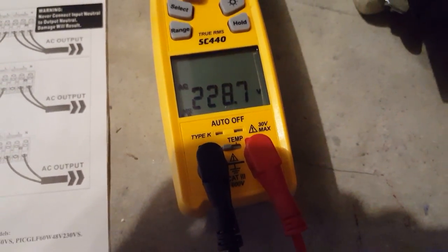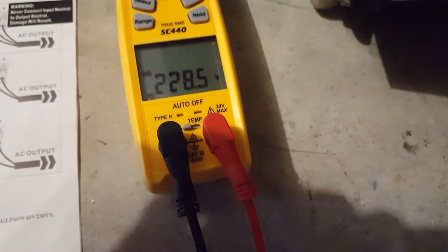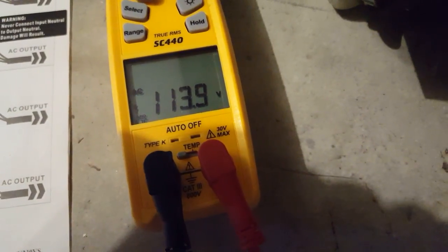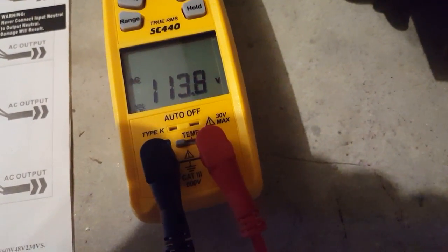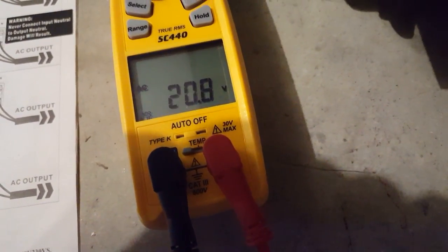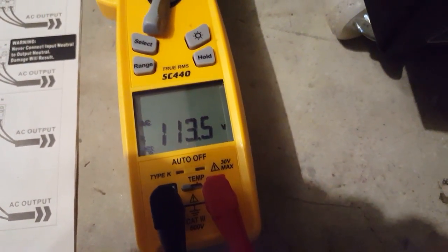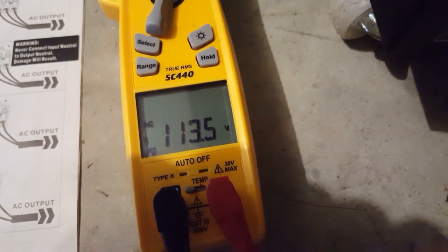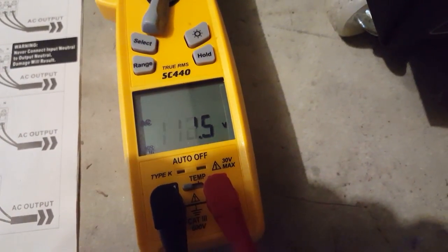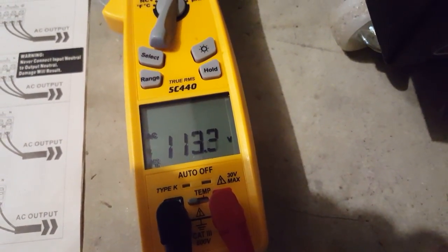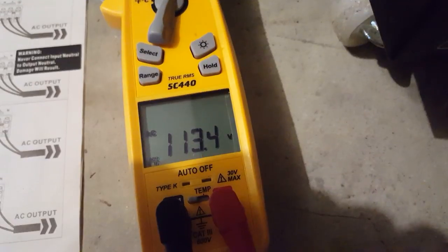What's different about this inverter versus other inverters, it can separate the voltage. So right here we were checking the voltage, right. So now I'm going to go to the neutral leg. And look, we got 113 volts. Let's stay on the neutral leg and go to the other leg, and it's another 113 volts. It stays at 113 volts and then it does another 113 volts.